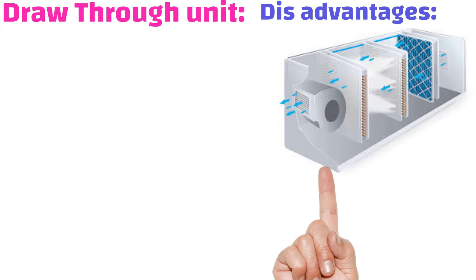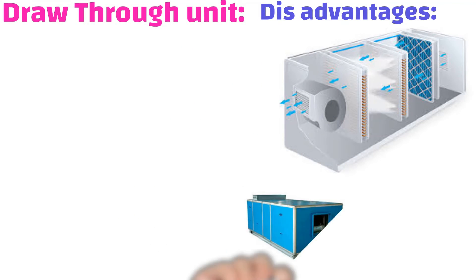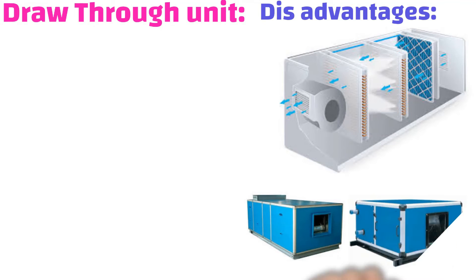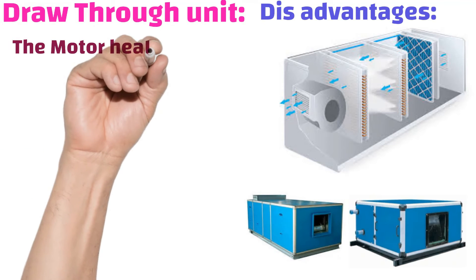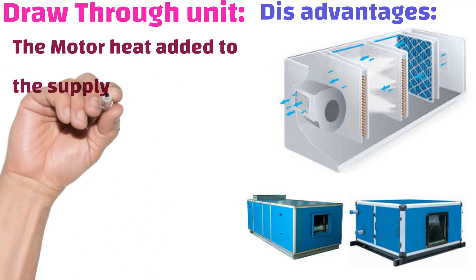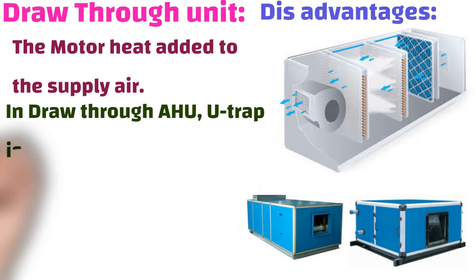Disadvantages of the draw through unit: In draw through AHU, the U-trap is on the negative pressure side. This will lead to smelly air being drawn back into the AHU when the U-trap is dried.